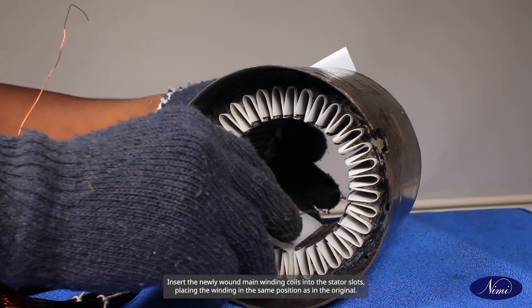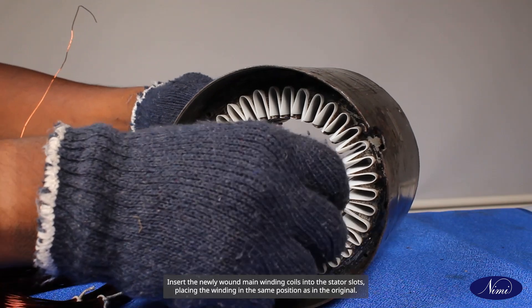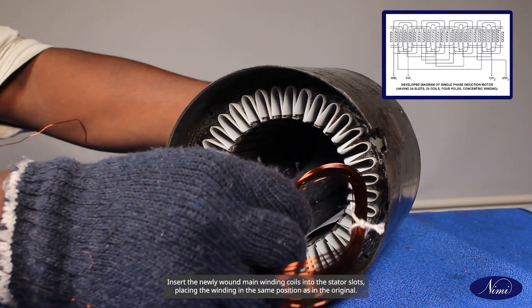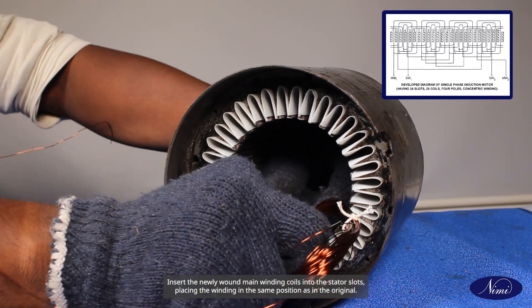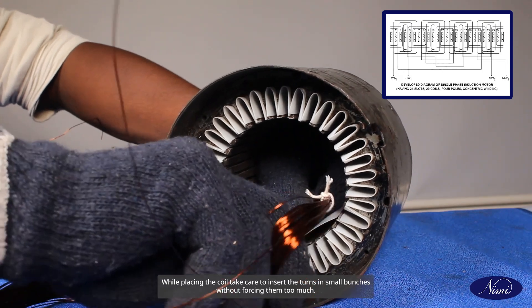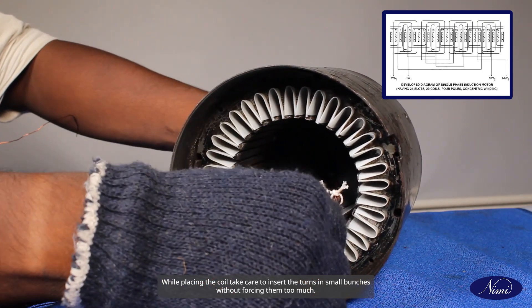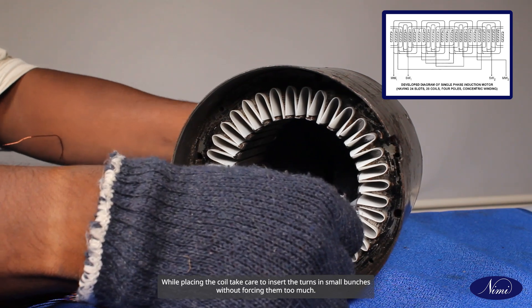Insert the newly wound main winding coils into the stator slots, placing the winding in the same position as in the original. While placing the coil, take care to insert the turns in small bunches without forcing them too much.